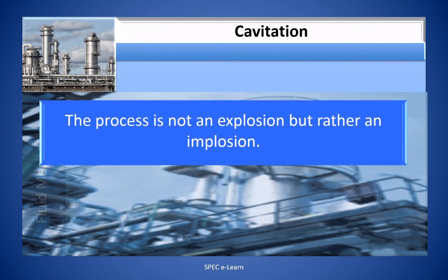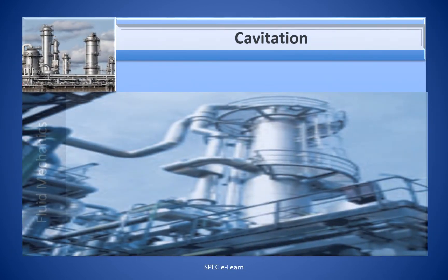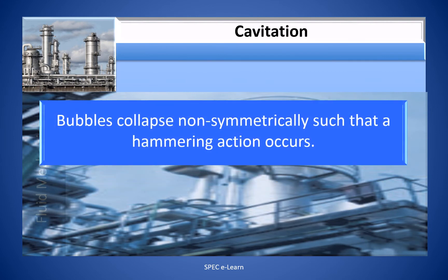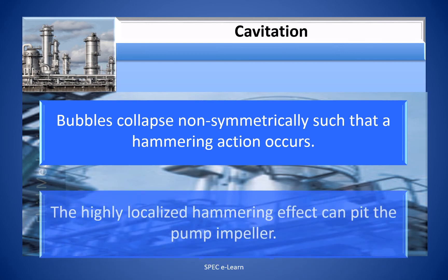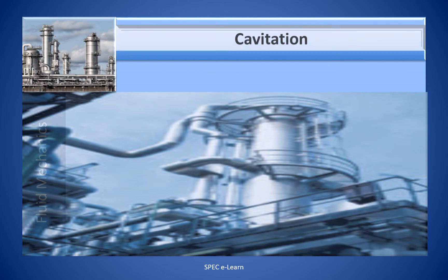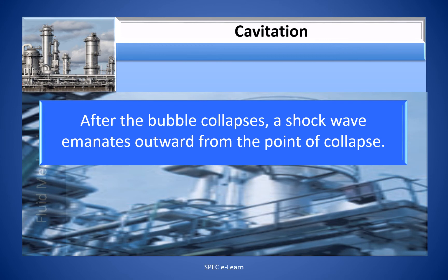The process is not an explosion but rather an implosion. Hundreds of bubbles collapse at approximately the same point on each impeller vane. The bubbles collapse non-symmetrically such that a hammering action occurs. The highly localized hammering effect can pit the pump impeller. After the bubble collapses, a shock wave emanates outward from the point of collapse. This kind of cavitation is known as NPSH available insufficiency.